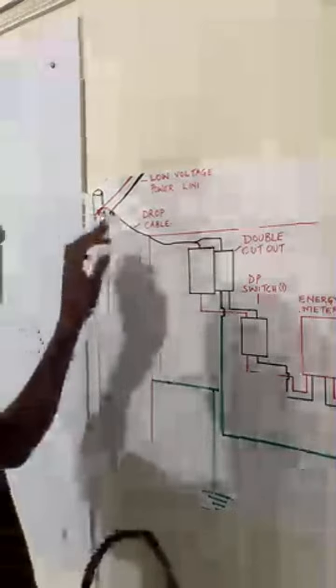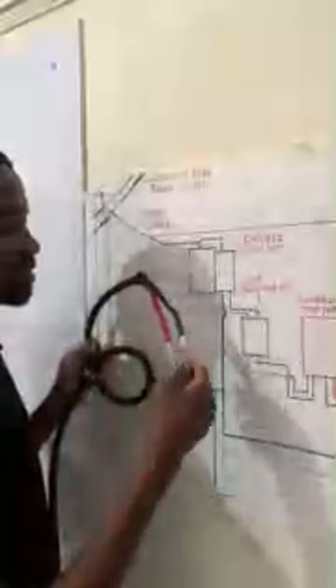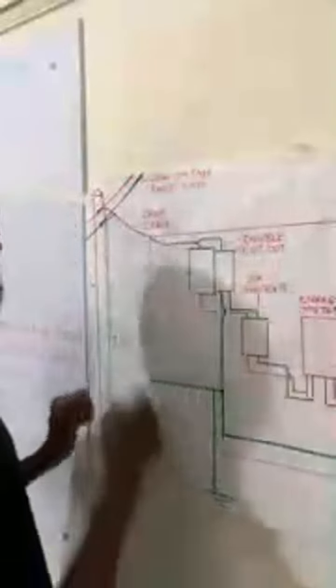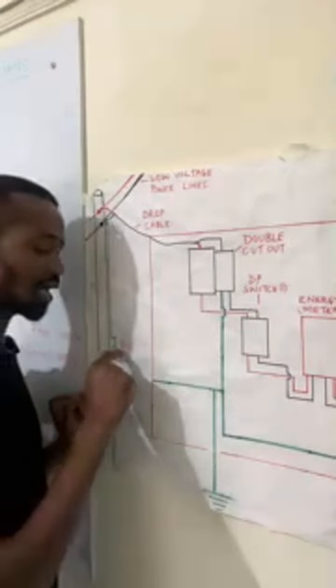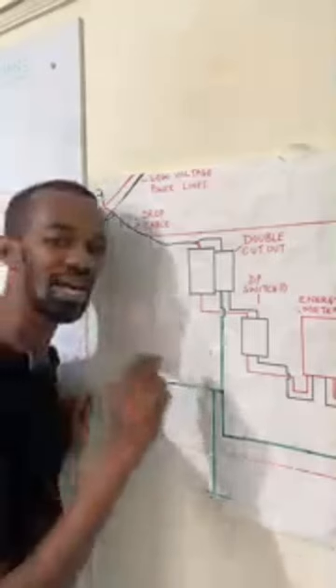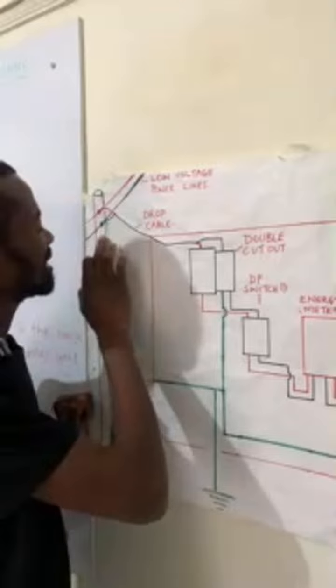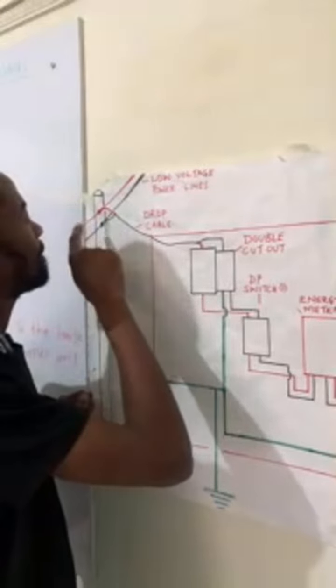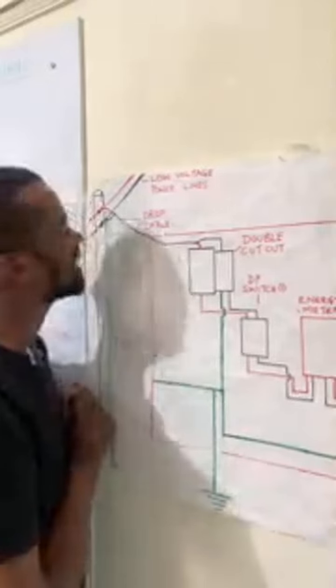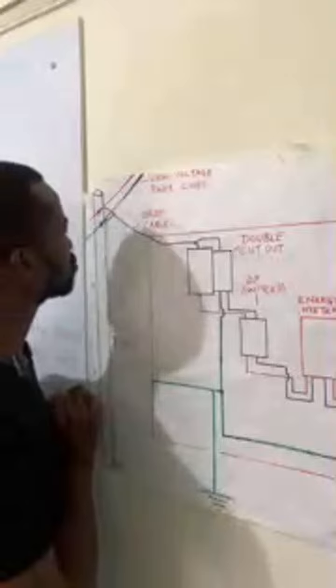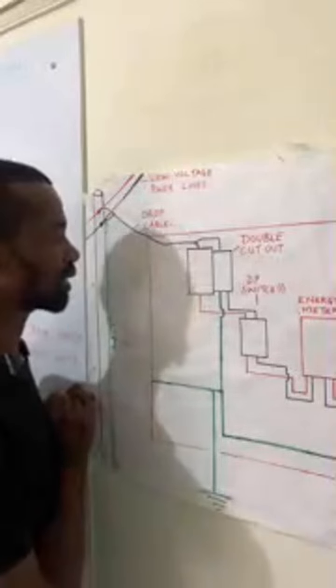So the connection is done there, and then it drops at this point. So the earthing is tapped at the output of the cutout, that is at the return section or the neutral section. Now, at this point here, the pole, we tap the PME, protective multiple earthing, from the neutral conductor. That is at the power lines that are on the national grid. Normally, the topmost part for a single phase connection is the live or the phase. If you are having two conductors on the national grid, we have two lines, and the topmost, regardless of where you are or the transformer that is supplying that area with power through those power lines, is usually a phase.